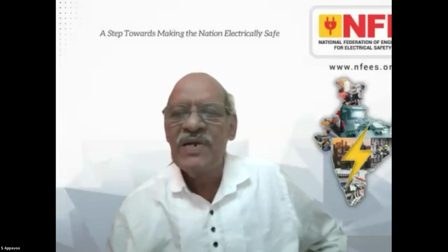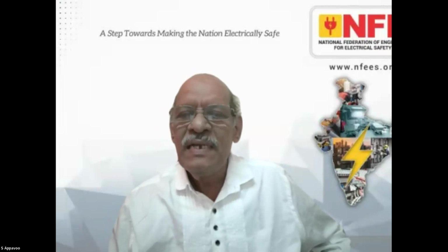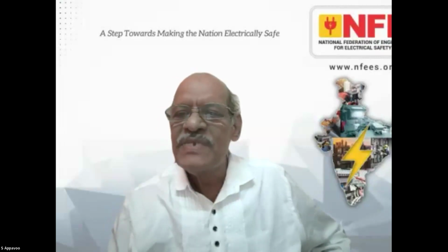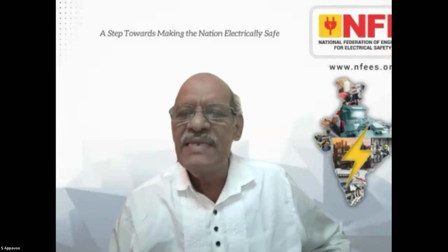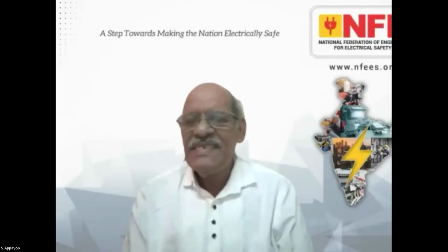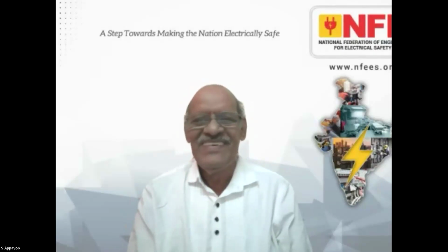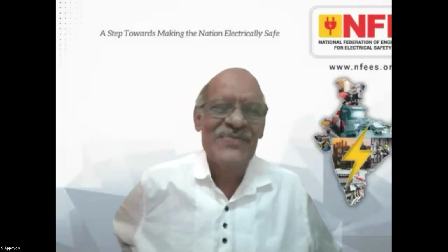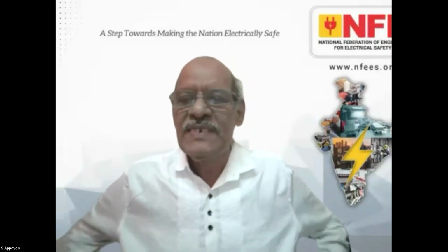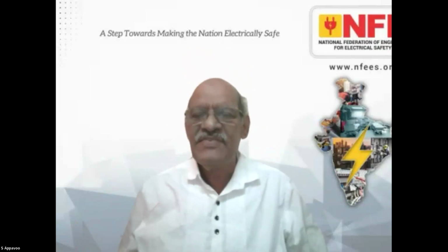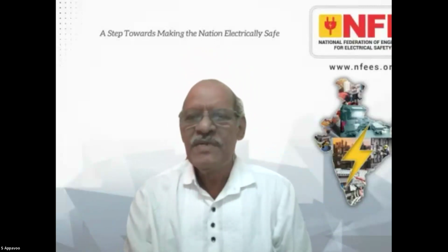Another question from Ved Prakash: can we connect the LPS earth pit connections with the substation main earth grid? If not, that's a problem. You are supposed to connect all these together, this is called equipotential bonding. Interconnection is the mantra here. People hesitate to connect and keep things separate, but that concept should go, it's a myth. We have to interconnect; unless we do, we can't achieve equipotential bonding.